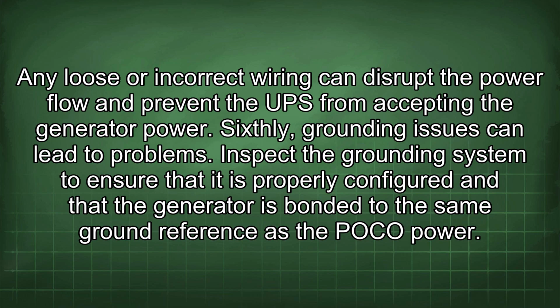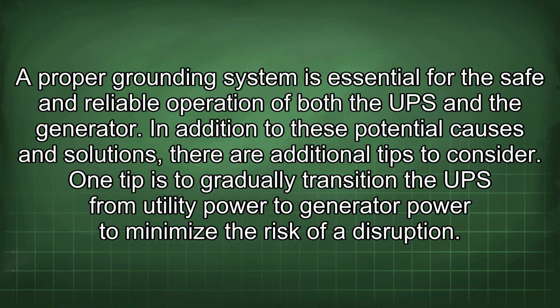Sixthly, grounding issues can lead to problems. Inspect the grounding system to ensure that it is properly configured and that the generator is bonded to the same ground reference as the POCO power. A proper grounding system is essential for the safe and reliable operation of both the UPS and the generator.